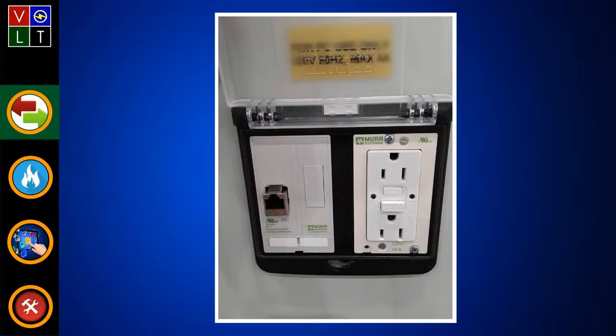And obviously, in this factory, per our specs, we're required to run 20 amp circuits to everything. We're not allowed to have a 15 amp circuit unless it's a 15 amp circuit for a reason. That piece of equipment has to call for a 15 amp circuit. Otherwise it has to be 20 amp.